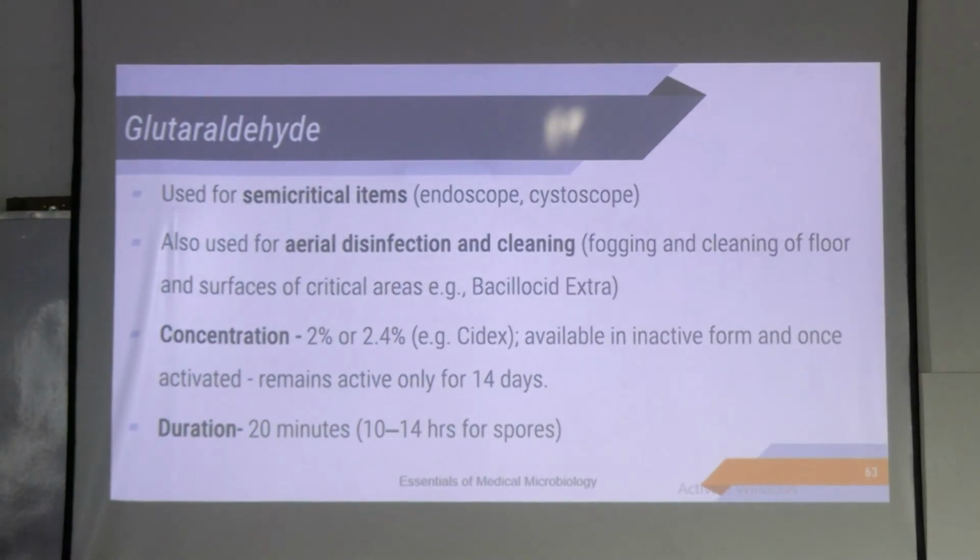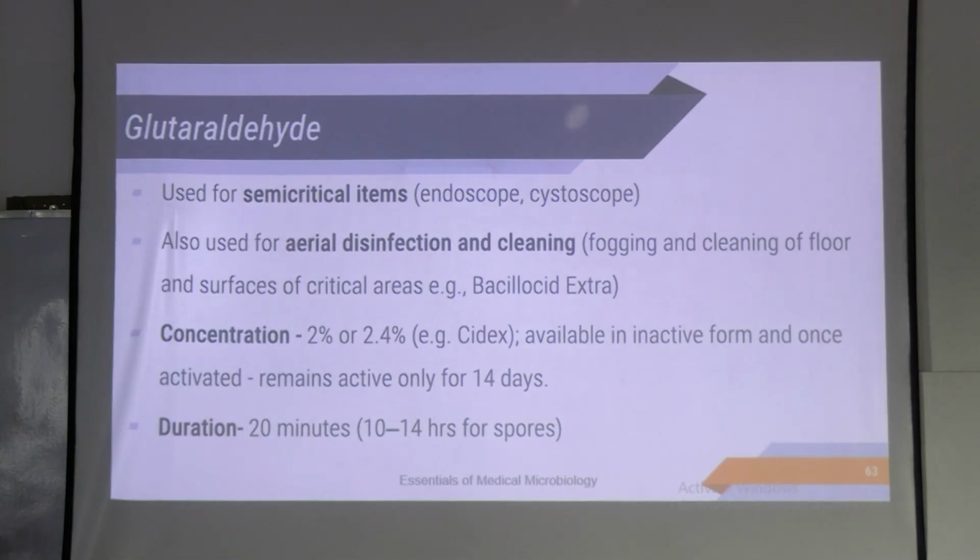That means suppose I have done bronchoscopy on one patient. After the procedure is over, the first thing I need to do is clean the bronchoscope and then put the bronchoscope inside a glutaraldehyde solution. The solution must have at least 2% glutaraldehyde, and after putting it inside the solution, it must be kept there for a minimum of 20 minutes. If both these factors are altered, then disinfection will not occur.